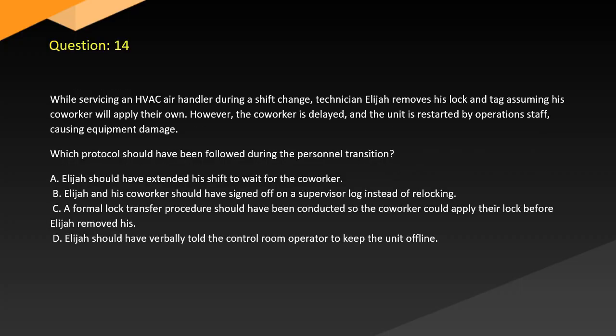Question 14. While servicing an HVAC air handler during a shift change, technician Elijah removes his lock and tag, assuming his coworker will apply their own. However, the coworker is delayed and the unit is restarted by operations staff, causing equipment damage. Which protocol should have been followed during the personnel transition? A. Elijah should have extended his shift to wait for the coworker. B. Elijah and his coworker should have signed off on a supervisor log instead of relocking. C. A formal lock transfer procedure should have been conducted so the coworker could apply their lock before Elijah removed his. D. Elijah should have verbally told the control room operator to keep the unit offline.